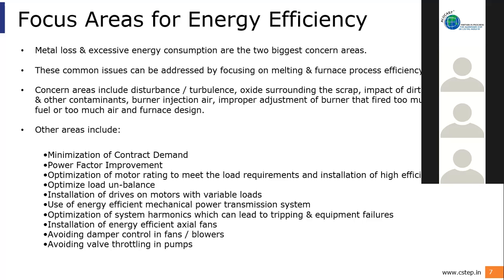Harmonics, another important area of concern for the units today. Now, as far as harmonics is concerned, there is no penalization from the grid as on date. But yes, this can lead to failures. This can lead to trippings if it is not addressed or not controlled at the right time.